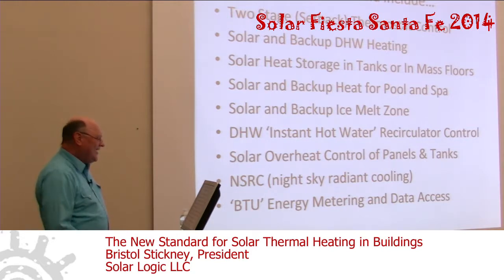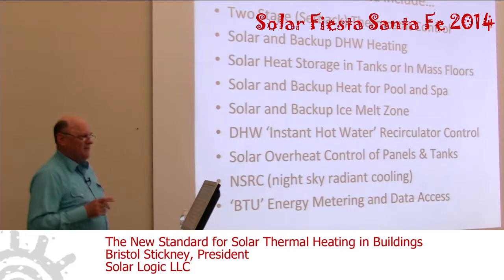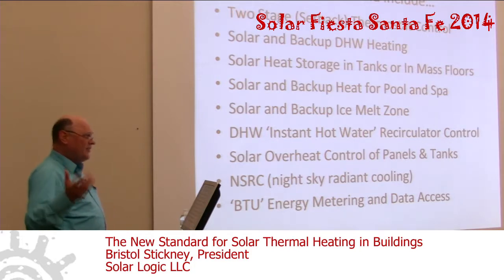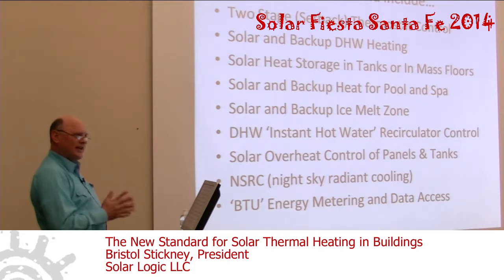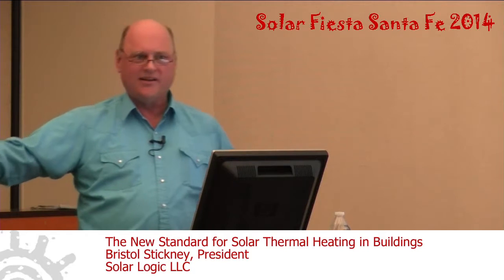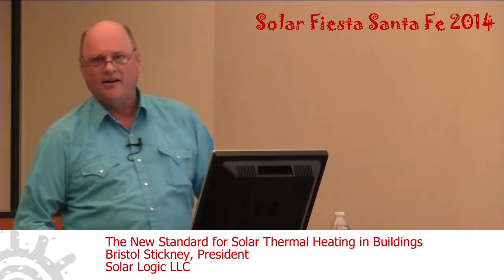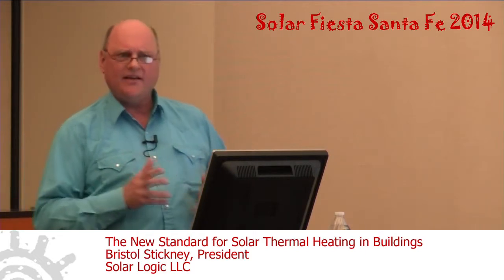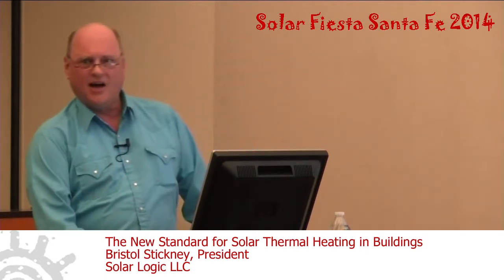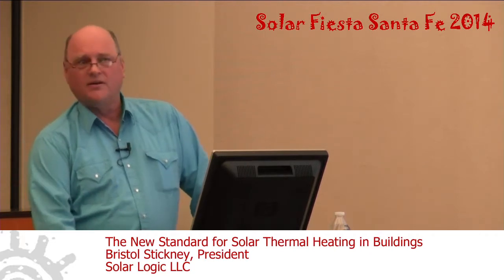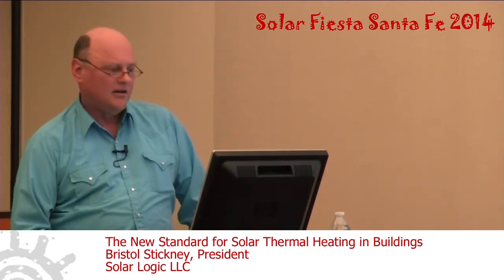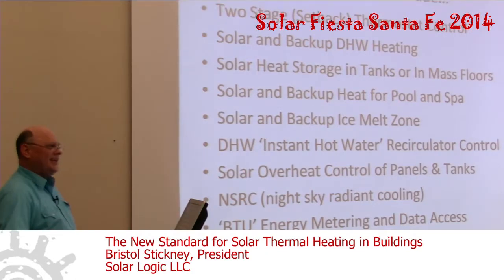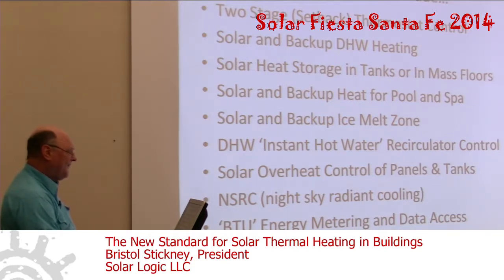But just quickly, if you don't control the instant hot water heat delivery pump, the pump that pumps heat out of your water heater over to your faucet so that you have instant hot water come out of your faucet, it will suck all the heat out of your hot water tank, and all the solar heat will be lost as waste heat going to your faucets in just a few hours every night. So this is a way of making the solar work better by controlling the instant hot water pump. And it's something that most solar controllers don't even think about, don't even mention, but it's super important. You can lose all of the heat in your solar hot water tank in just a few hours if your instant water pump is out of control.